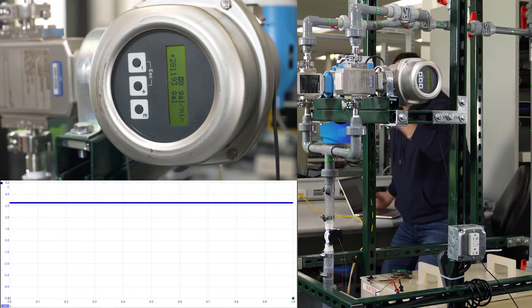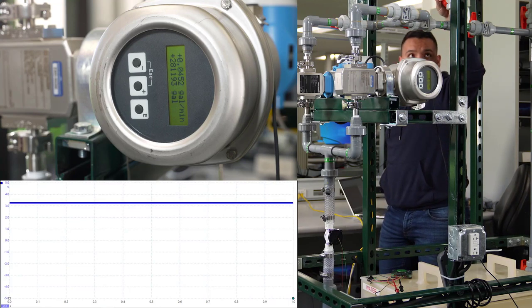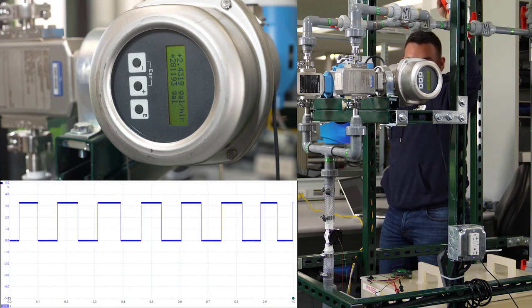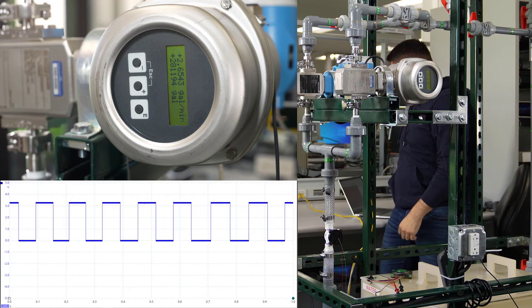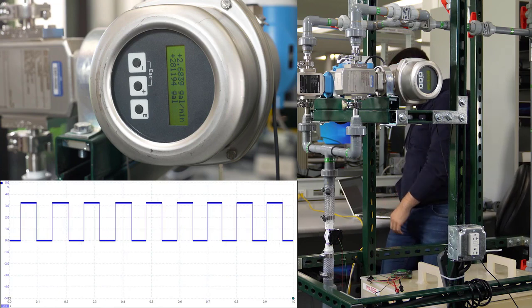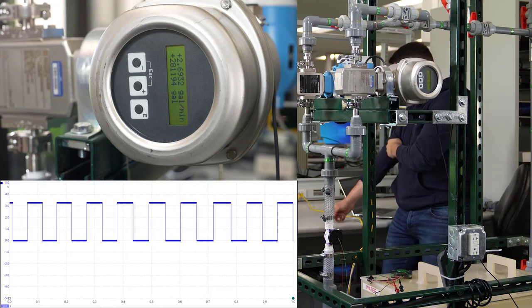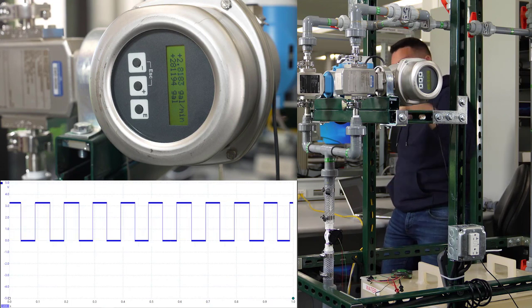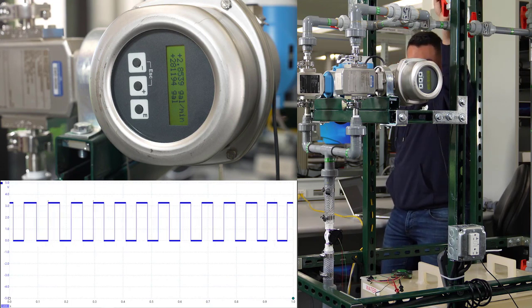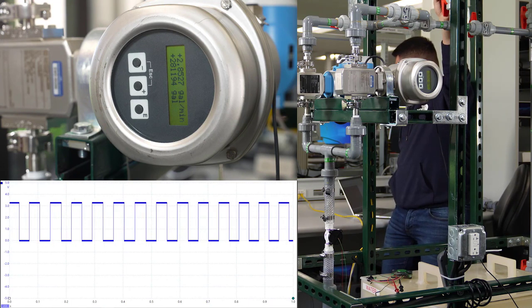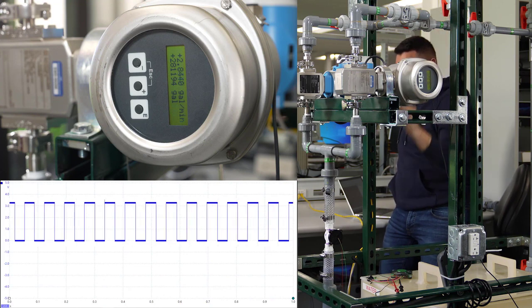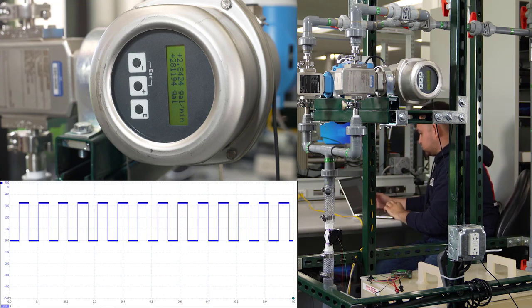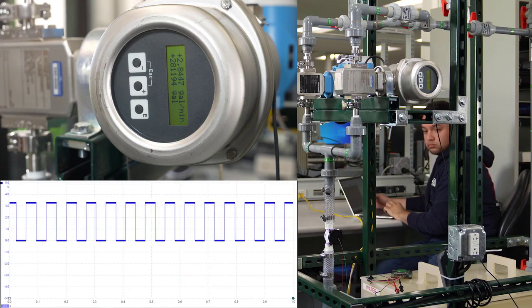Here, we are able to verify that as we allow the water to flow, we can observe a switching frequency in our Hall sensor output. When we increase the flow, we can observe that our Hall sensor's frequency has risen. When several more data points are collected, we are able to verify a linear behavior and are able to create a correlation formula that converts the output frequency of the Hall sensor to a GPM or LPM flow measurement with a plus or minus 1% accuracy.